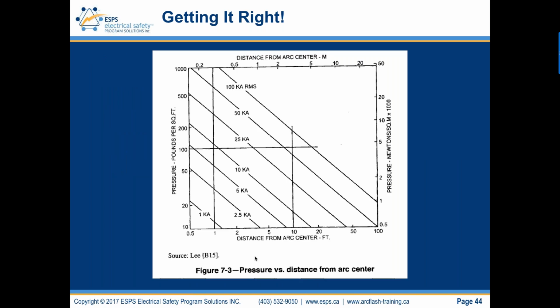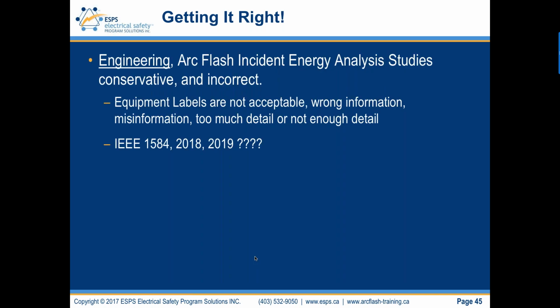And there's the graph from Dr. Ralph Lee again. Arc blast pressure is related to distance and arcing fault current, not incident energy. Equipment labels. I'm going to show some examples to you right now. This has propagated, and there are probably, unfortunately, millions of labels across North America that are not appropriate for the worker to read or see, with issues interpreting the label as well. So wrong information, not acceptable.